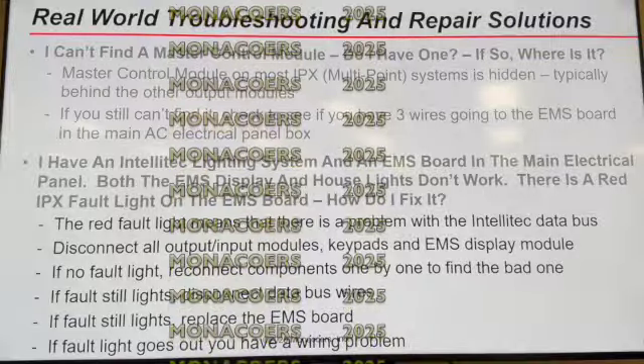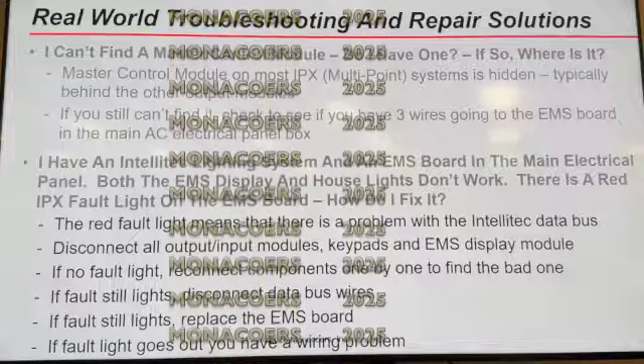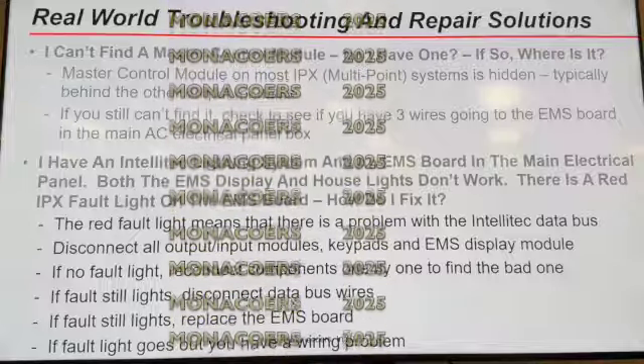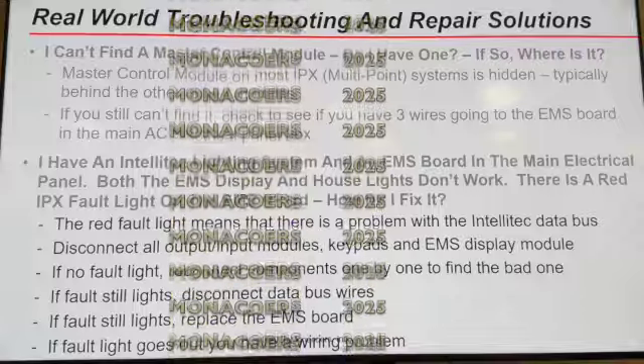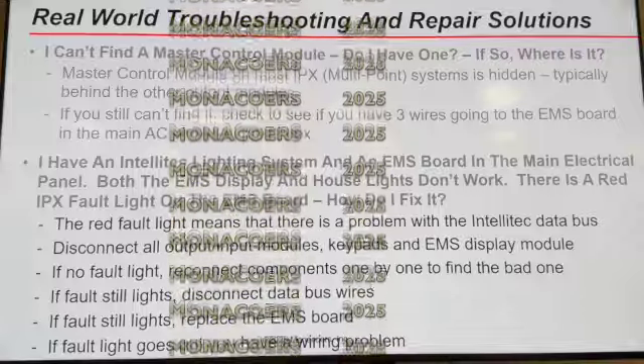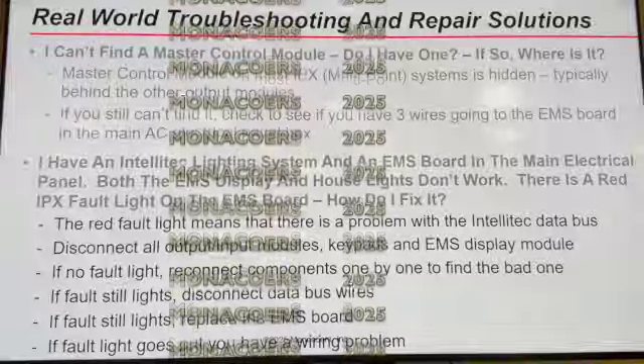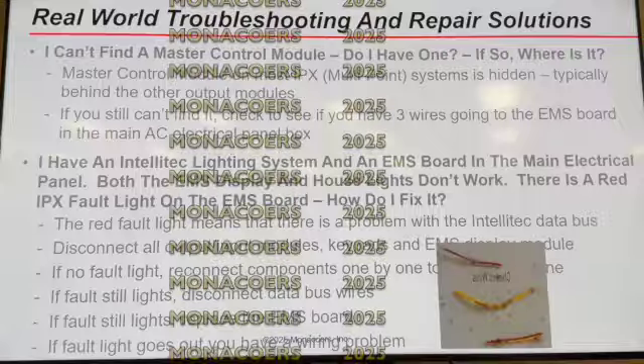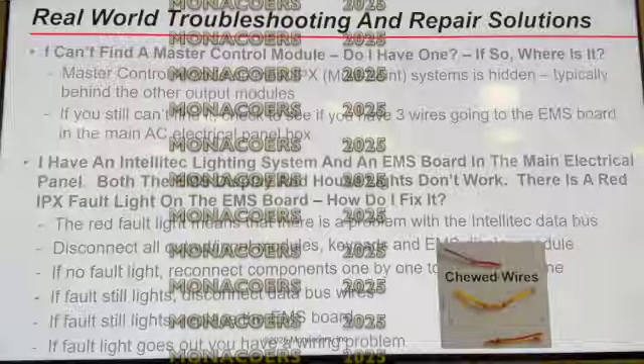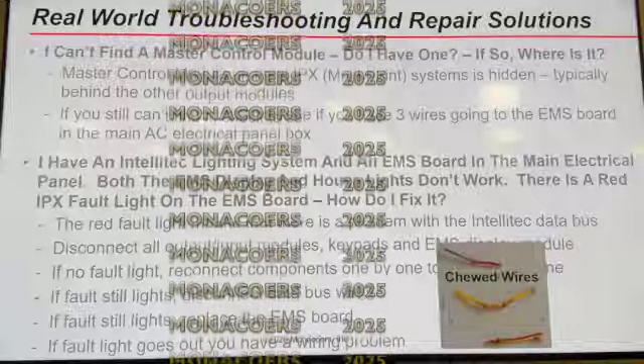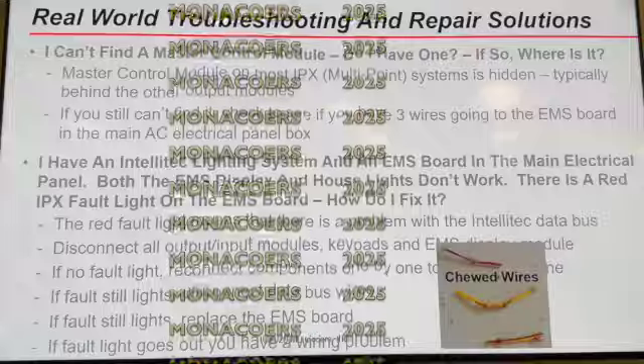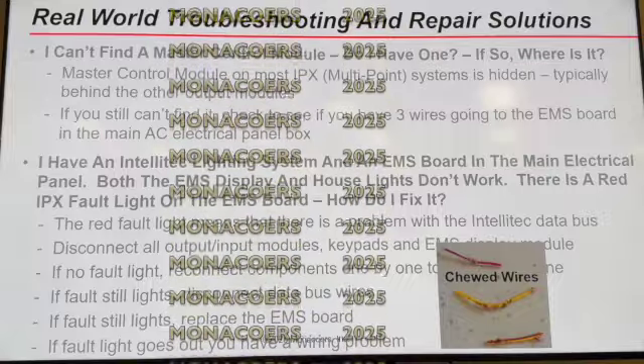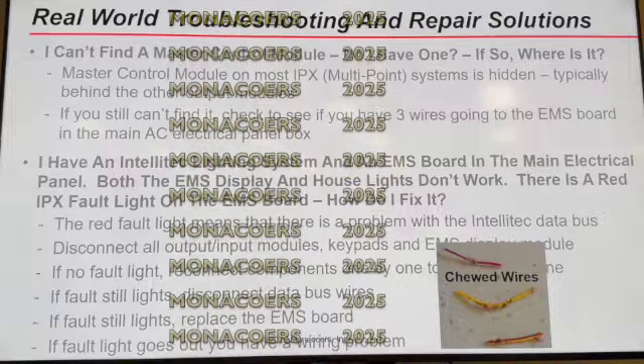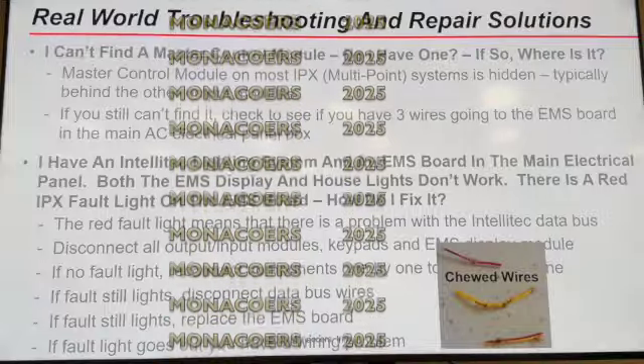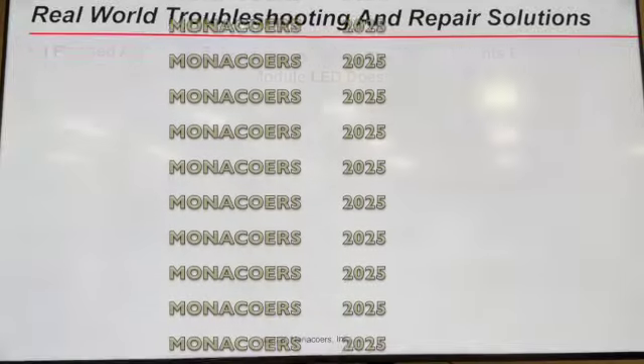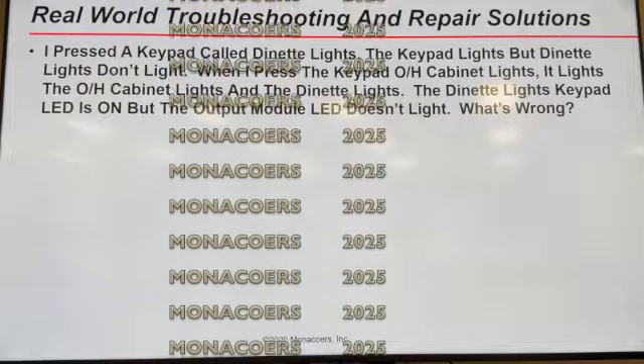If the fault light still stays on, you disconnect the data bus wire. If the fault light still stays on, you have a bad EMS. If the fault light goes out, you have a wiring problem. And guess what - they found a wiring problem. Some of the wiring got chewed, and that's why the red EMS light came on. There was a long thread about this posted maybe about six months ago. He finally fixed it - he was smart, he changed it to put an IPX in instead, and it still didn't work.